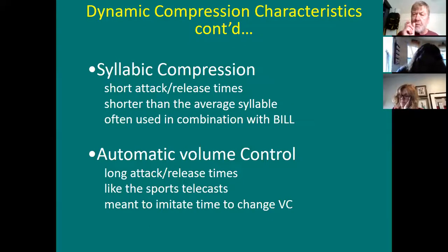And when you remember Bill, bass increase at low levels, Bill is simply WDRC confined to the bass frequencies. It's WDRC mainly below 1,000 hertz. So when the sound is loud coming in, you're going to get a reduction of low frequency gain. And when the sound becomes softer, you get an increase of low frequency gain, assuming that background noise is low frequency.